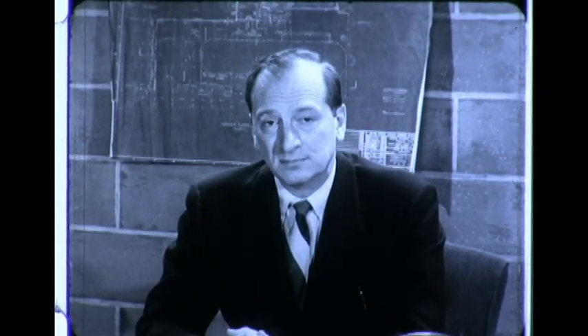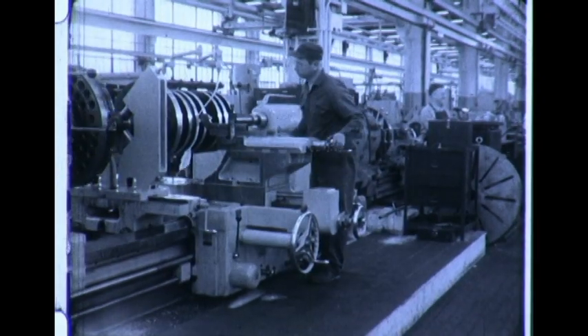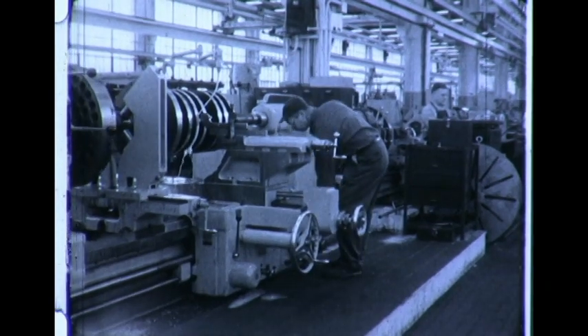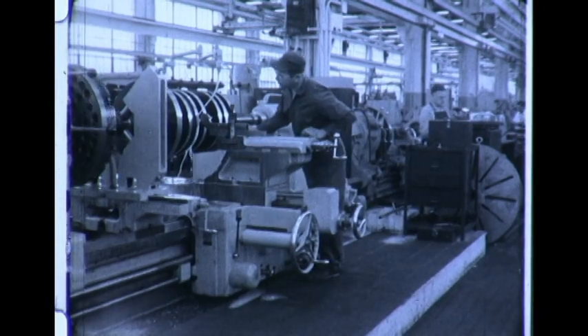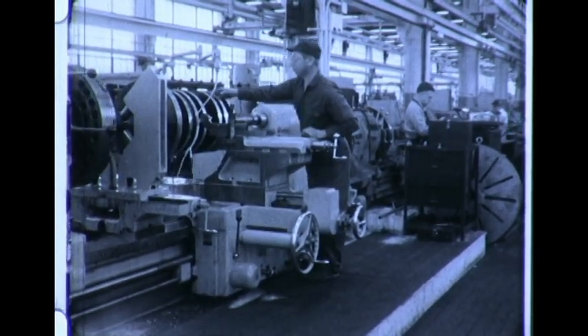What do you consider the most precise operation in your manufacturing cycle? That's a tough one. Of course, everything has to work just right when one of these machines goes into service. I guess you might say the rotor assembly is as precise as you could find. The rotor itself is machined within very close tolerances. The dovetails on the wheels and the shaft diameter, for instance, must be within five-tenths of a thousandth before the rotor is ready for the next operation.